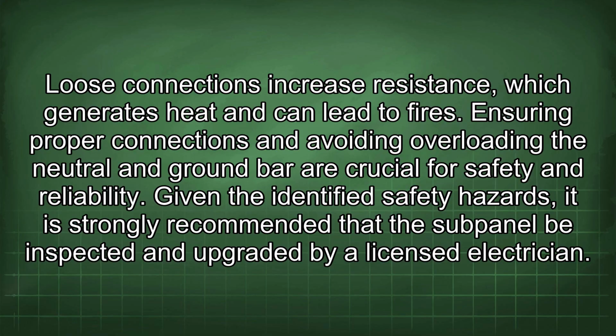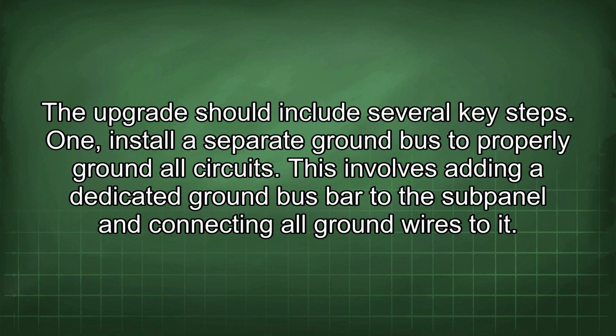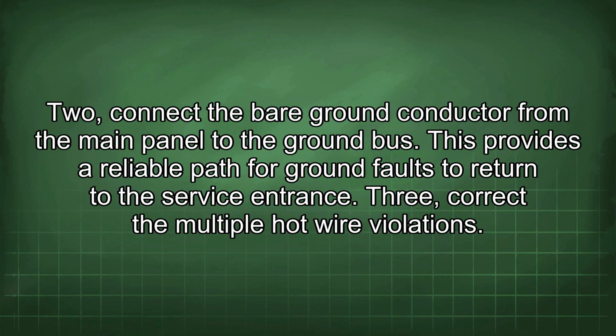Given the identified safety hazards, it is strongly recommended that the subpanel be inspected and upgraded by a licensed electrician. The upgrade should include several key steps. 1. Install a separate ground bus to properly ground all circuits. This involves adding a dedicated ground bus bar to the subpanel and connecting all ground wires to it. 2. Connect the bare ground conductor from the main panel to the ground bus. This provides a reliable path for ground faults to return to the service entrance.